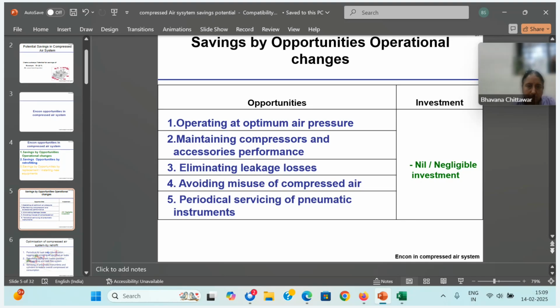So maintaining compressor performance is the main key. You have to check the temperature rise, the air-oil pressure drop across the air-oil separator, then the cooling system and accessories like coolers, performance of coolers and air dryer, then oil filter performance, non-return valve performance. Each and every accessory plays its own role. Only if you maintain properly in total can you achieve good performance for the total system.